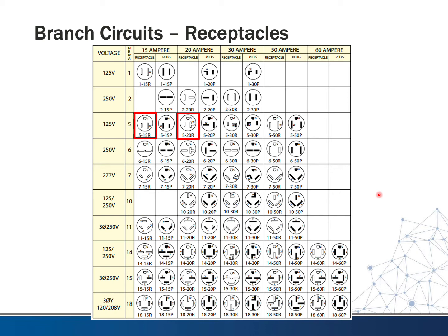Another one that might be familiar is the NEMA 10-30R, rated for 240 and 120 volts, with two phases and a neutral — this is a three-pronged dryer plug. If not this one, it would probably be the 14-30R, which has the same voltage and amperage but also has a ground terminal, so it has four prongs instead of three. Welding machines often take a 50 to 60 amp plug, so you might run across some of these.